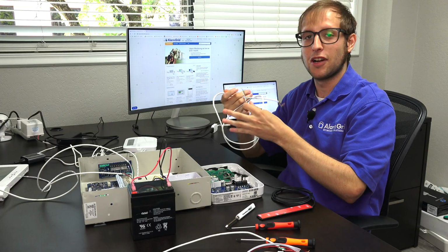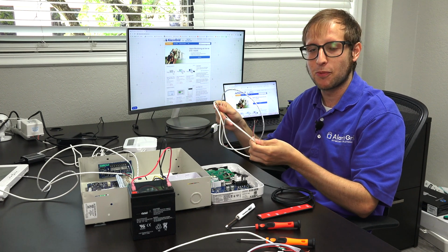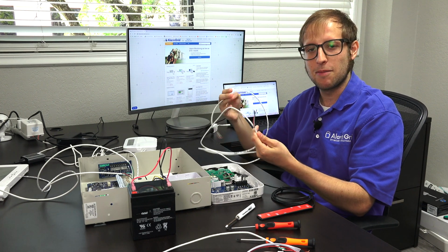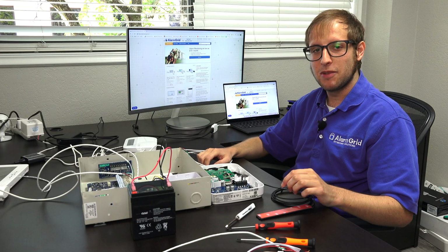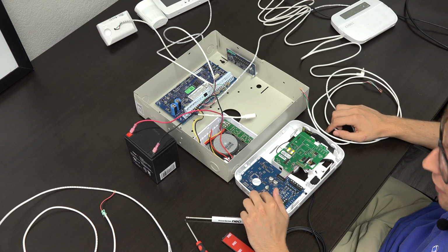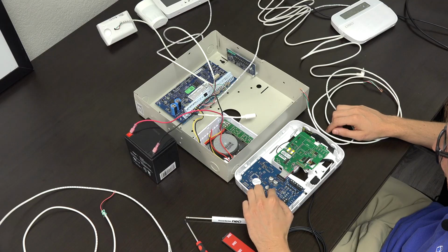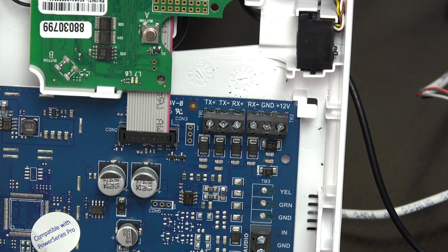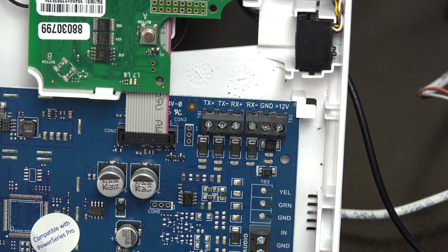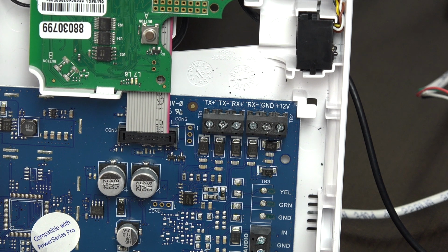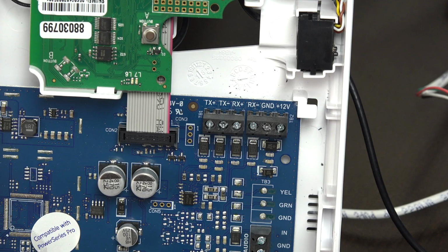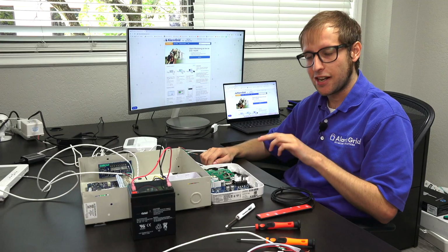There we go. We have a 22-gauge wire. 18-gauge also works great. We prefer stranded wire because it's easier to work with. So you see on the communicator, we have our terminal block here. We're actually going to use all 6 of these connections here. We have TX plus, TX minus, RX plus, RX minus, and then we have the power connections, the ground and the 12 volt. For the 4-wire connection, we're going to be working with the TX and the RX ones.